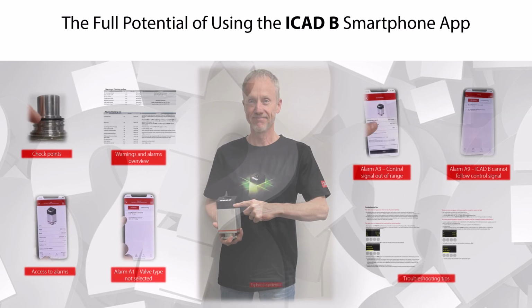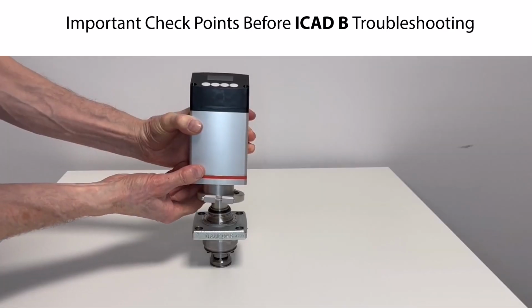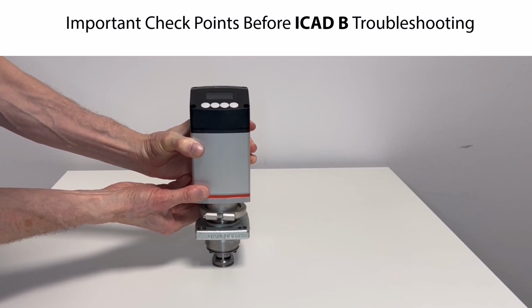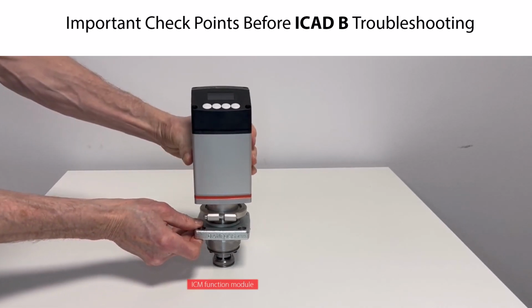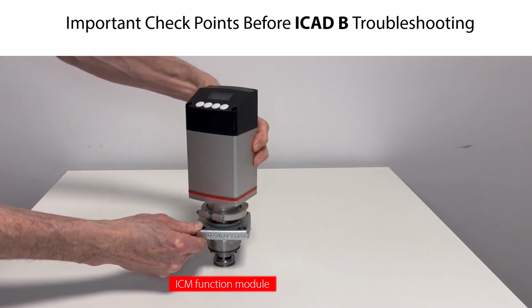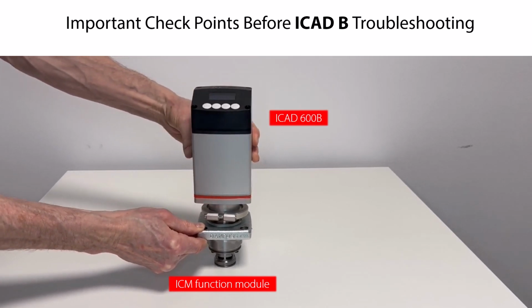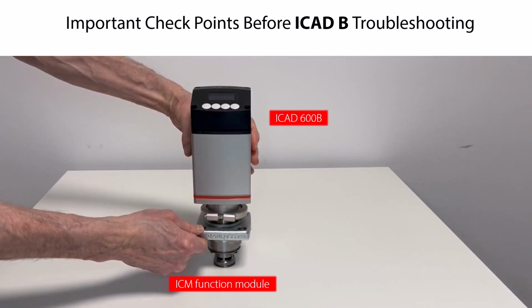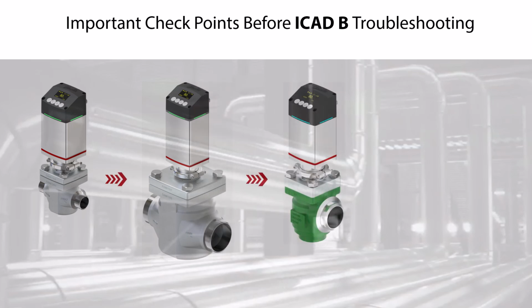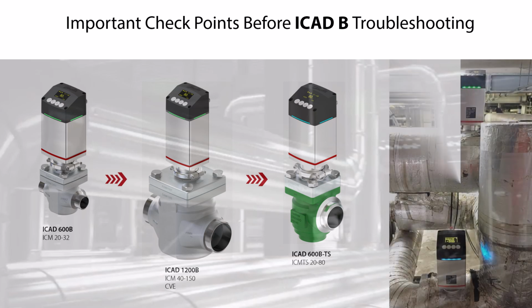So keep watching this video to learn more about these objectives and explore the full potential of using the ICAD B smartphone app. In this video, we demonstrate the ICAD B troubleshooting using an ICM function module located on a table, as seen here, and we mount the ICAD 600B model onto this ICM function module. However, the troubleshooting procedure is the same for all ICAD B models and all suitable valves, and the troubleshooting procedure is the same with a suitable valve and ICAD B already located in a refrigeration system.